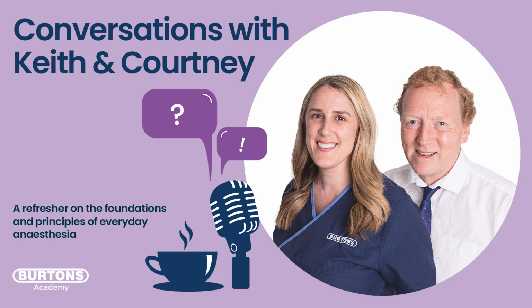And what you're looking for is 2 oscillations. Like it goes down, up, and then it goes back flat again. If you get what looks like up, down, up, down, up, down, up, down, getting smaller and smaller and smaller, that's called ringing. And if that's the case, then you've got an underdamped system. Okay, and if you've got an underdamped system, again, it's going to be a compatibility problem.